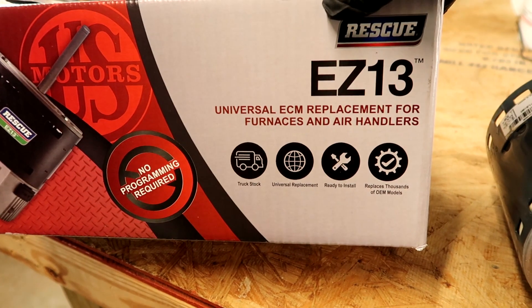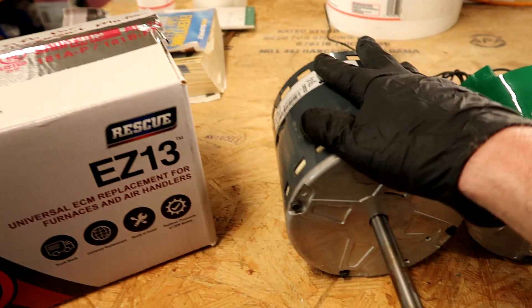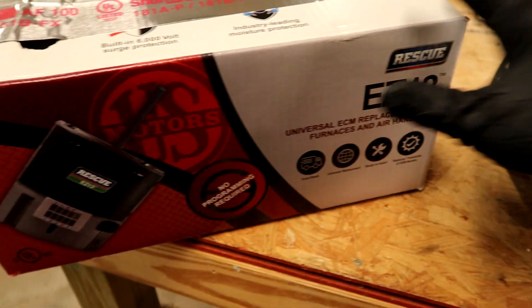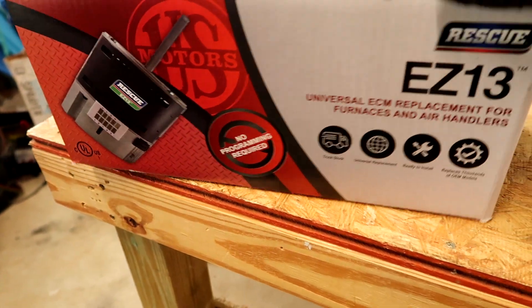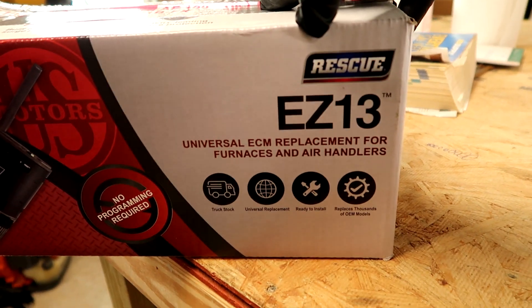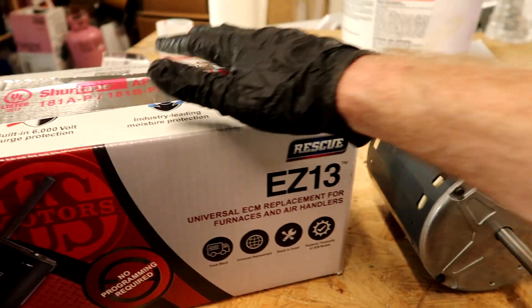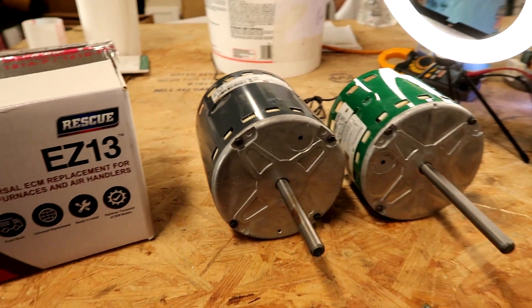Johnstone gave me a universal ECM replacement. I prefer to go back with what's in there — a Genteq X13, three-quarter horsepower — but they said this will work. That was Thursday, today is Saturday and so far so good. What I went back in there with is the EZ13 universal ECM replacement. Alright guys, videos are going to start pumping out — a lot of HVAC stuff. Thanks for watching, see you in the next one.